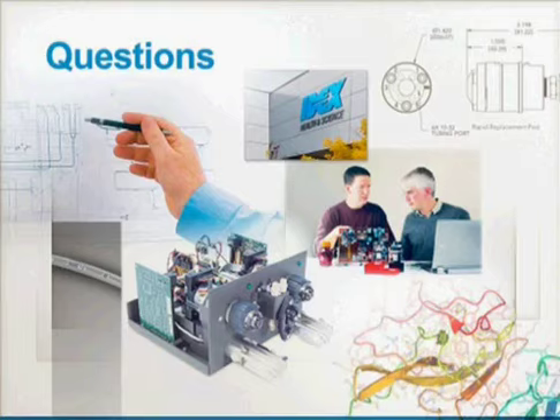I think, just to follow that up a bit further, you raise a valid point. It's very difficult to get a gold standard at 100 nanoliters per minute largely because of all those environmental effects, whereas standards for flow are much easier to achieve at milliliter per minute and above flow rates. So you're right. For most applications, it seems like precision is the name of the game.